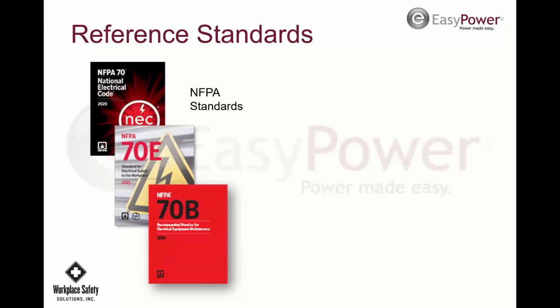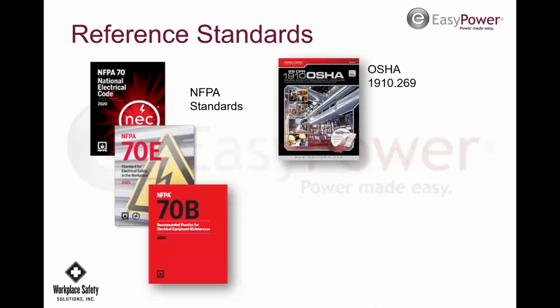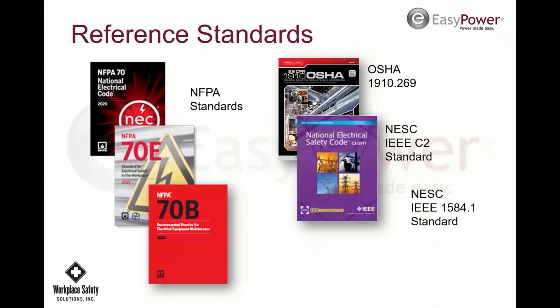70B is a great document as well. It's a maintenance guide, and it gives you some ideas on what to do for maintenance. A lot of civil litigations are basically due to lack of maintenance, whether it's damage, injuries, or fatalities. So for OSHA, there's 269, subpart S, subpart K, subpart V, and 1910.137. They're all electrical regulations we can follow, but they all come from the standards. The National Electric Safety Code is more of a utility or utility-like work standard for medium voltage.